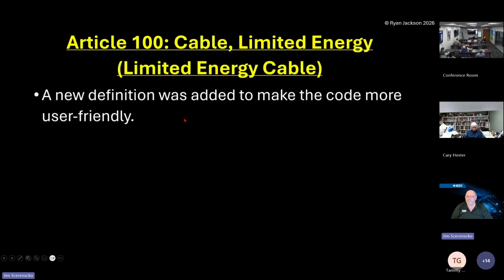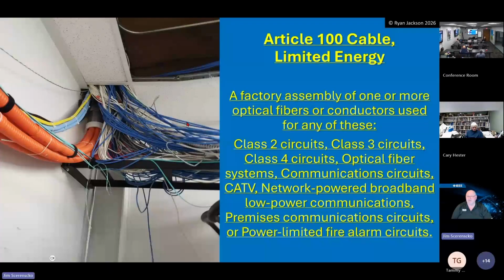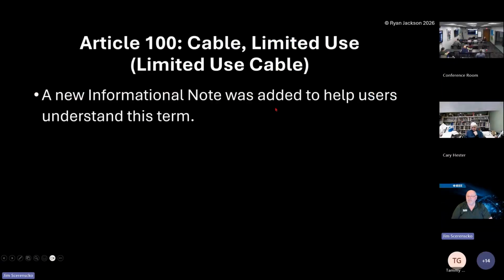A new definition was added for cable, limited energy cable systems. A factory assembly of one or more. It's a horrible looking picture right there. I mean, whoever installed that should be ashamed. A factory assembly of one or more optical fiber or conductors used for any of these: Class 2, Class 3, Class 4 circuits, optical fiber systems, communications, CAT, TV, network powered broadband, low power communications, premise communication circuits, or power limited fire alarm. So a limited energy definition now in the code.